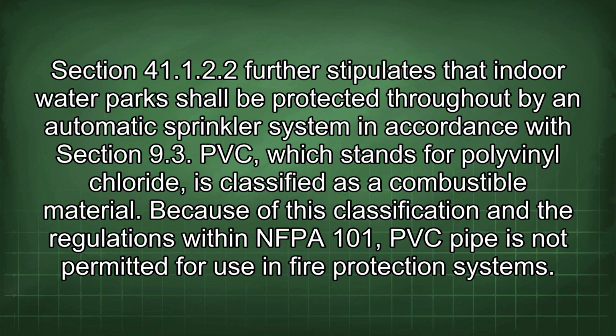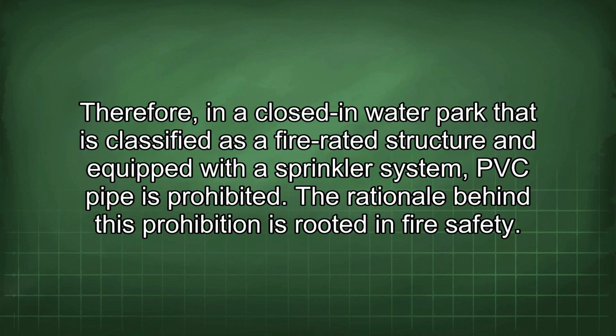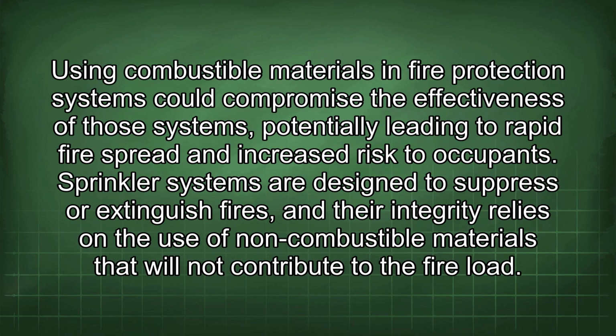Because of this classification and the regulations within NFPA 101, PVC pipe is not permitted for use in fire protection systems. Therefore, in a closed-in water park that is classified as a fire-rated structure and equipped with a sprinkler system, PVC pipe is prohibited. The rationale behind this prohibition is rooted in fire safety. Using combustible materials in fire protection systems could compromise the effectiveness of those systems, potentially leading to rapid fire spread and increased risk to occupants.